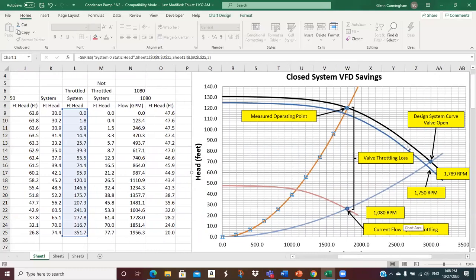Okay? So the design point on the system is out here. So if you open the valve all the way open, the design point was 3,000 GPM. But these guys were, what is that? That's about 1,800. Looks like about 1,800 GPM and operating on this pump curve. Okay, well, so you put that in PSAT, and let's see, throttled system curve.